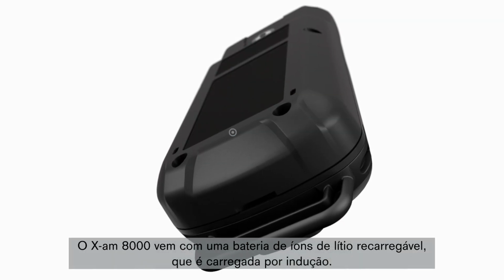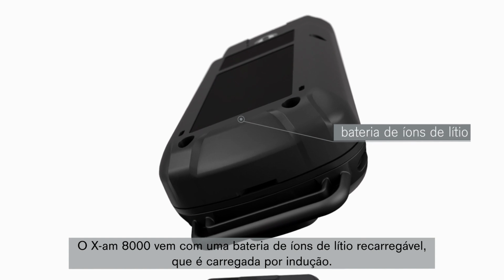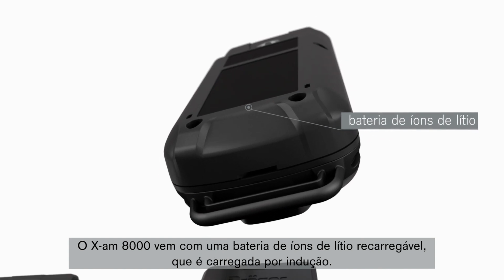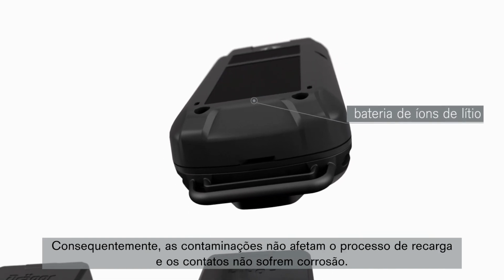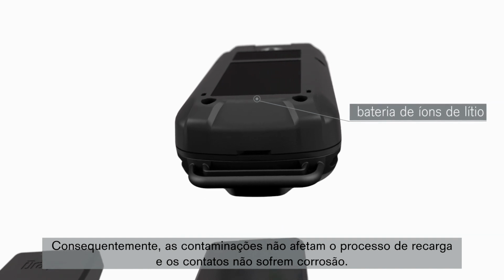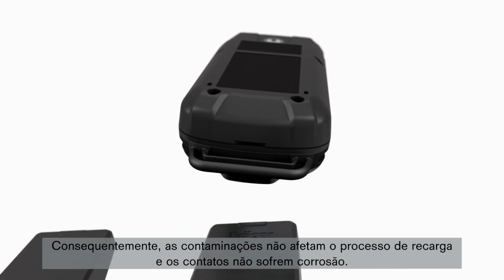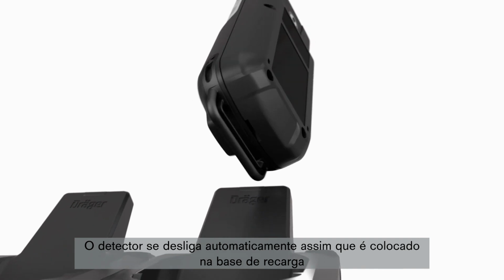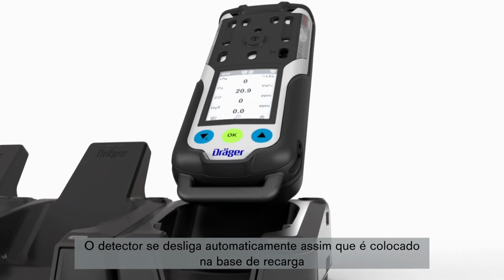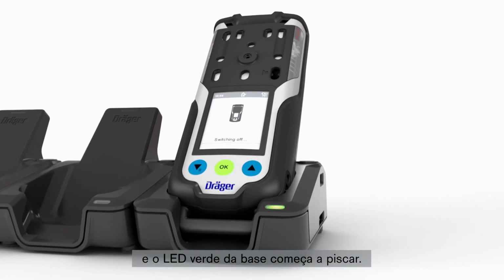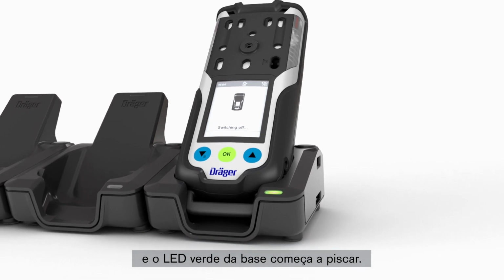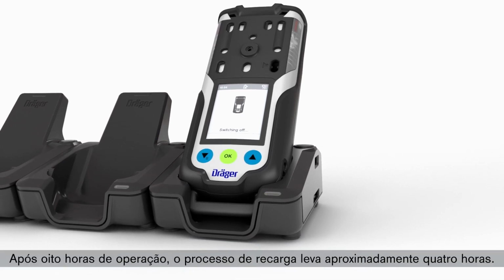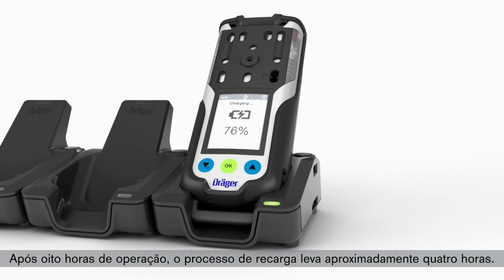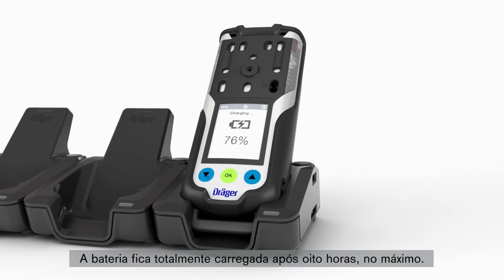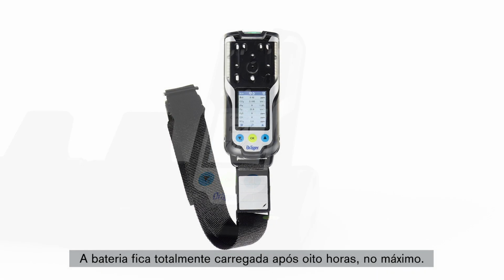The X-am 8000 is equipped with the rechargeable lithium-ion battery, which is charged inductively. Consequently, contaminations have no effect on the charging process and the contacts cannot become corroded. The gas detector switches off automatically as soon as it is placed in the charging cradle and the green LED on the cradle starts to flash. After 8 hours of operation, the charging process takes approximately 4 hours. The battery is fully charged after 8 hours at the latest.